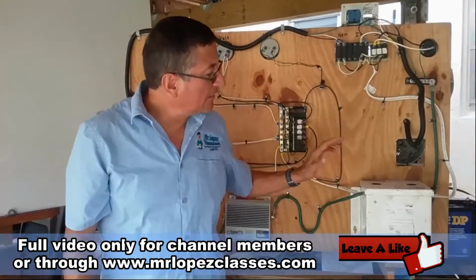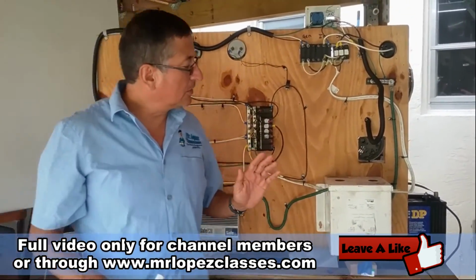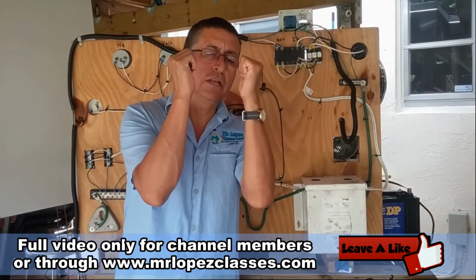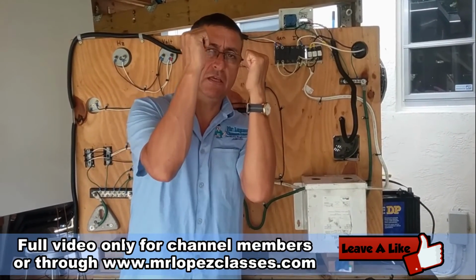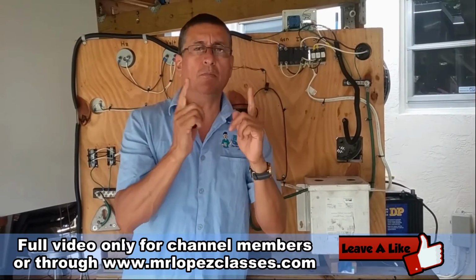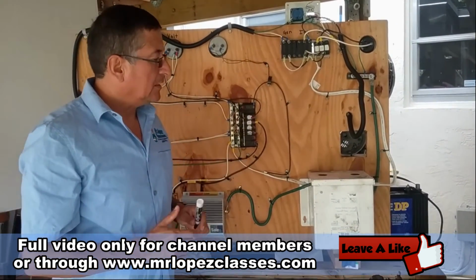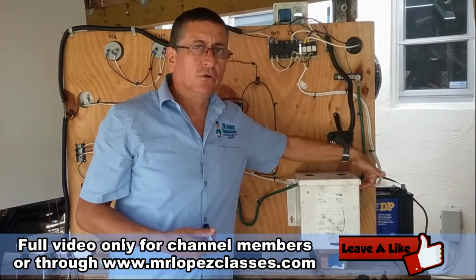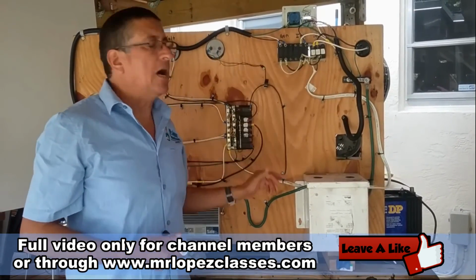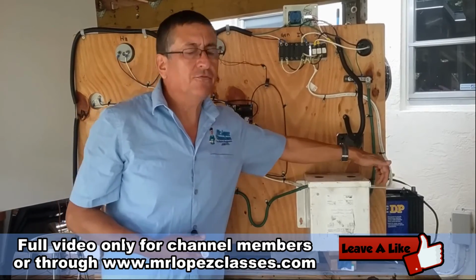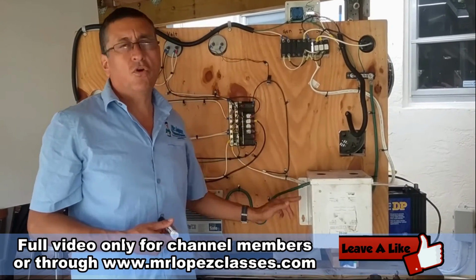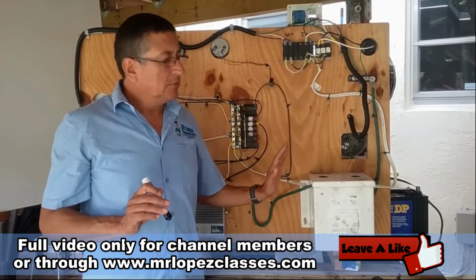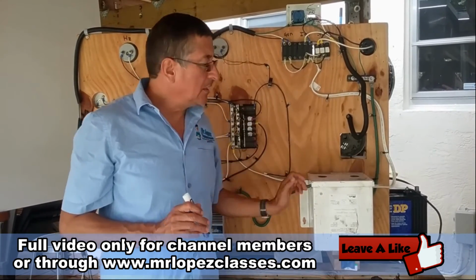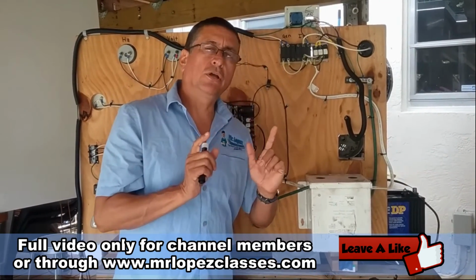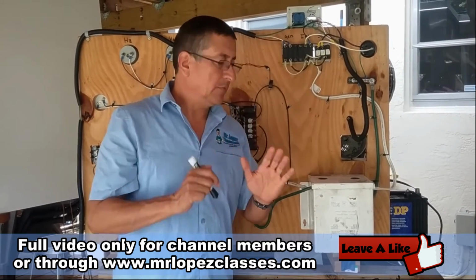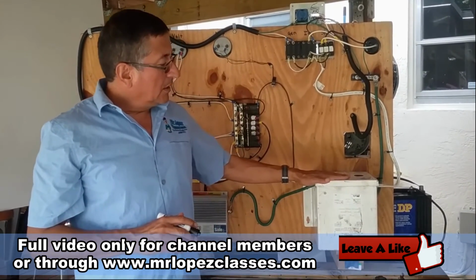In this particular case, I have an isolated transformer. Remember, the isolated transformer has equal turns on both sides, primary and secondary. What does that mean? If I have 120 volts at the input, I have 120 at the output. If I have 240 at the input, I have 240 at the output. The voltage is exactly the same because the number of turns in both coils, primary and secondary, are the same. This is the isolated transformer.